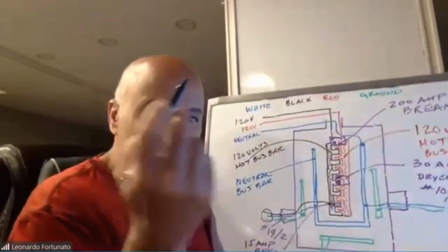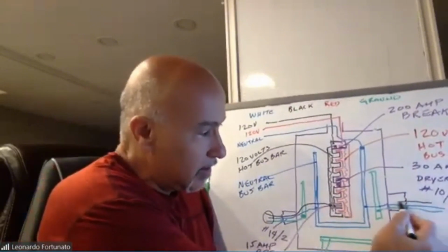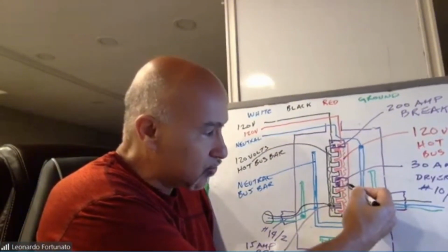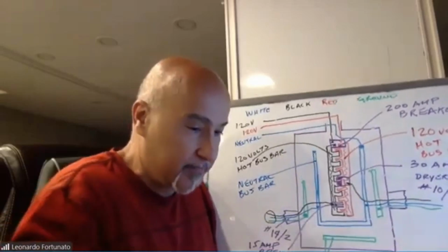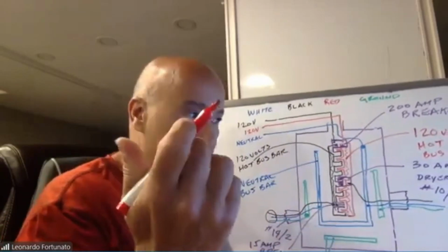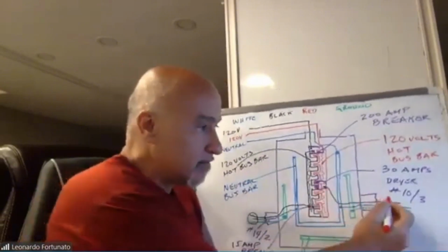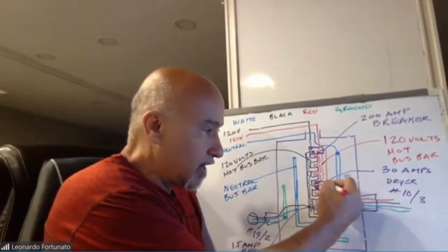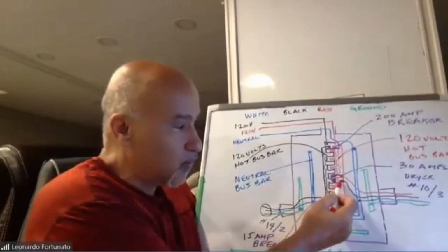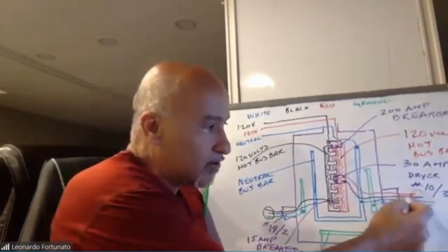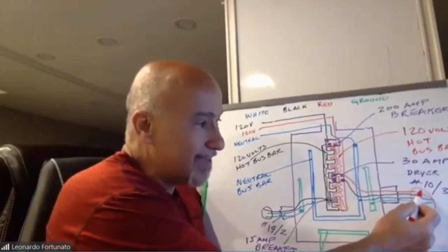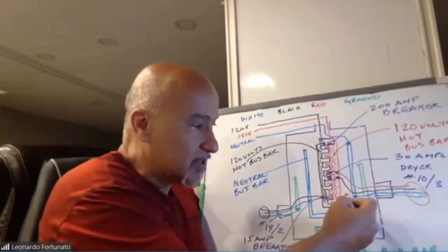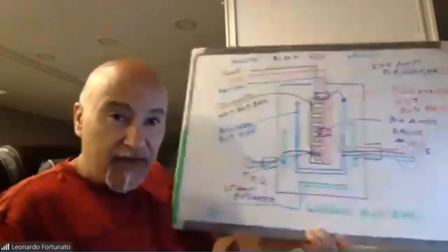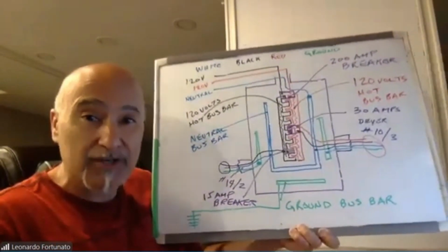That leaves us with 120 volts with the black wire. I'm going to bring it in and connect it to one side of my breaker. 120 volts with the red wire, and I'm going to connect it there. So now I've got 120 volts, 120 volts. They are now going to my dryer. 120, 120, that's 240. And the neutral brings the signal back, and the ground. Fair enough, ladies and gentlemen? Did you see how we made that connection? I'd like to do a little bit of a review.